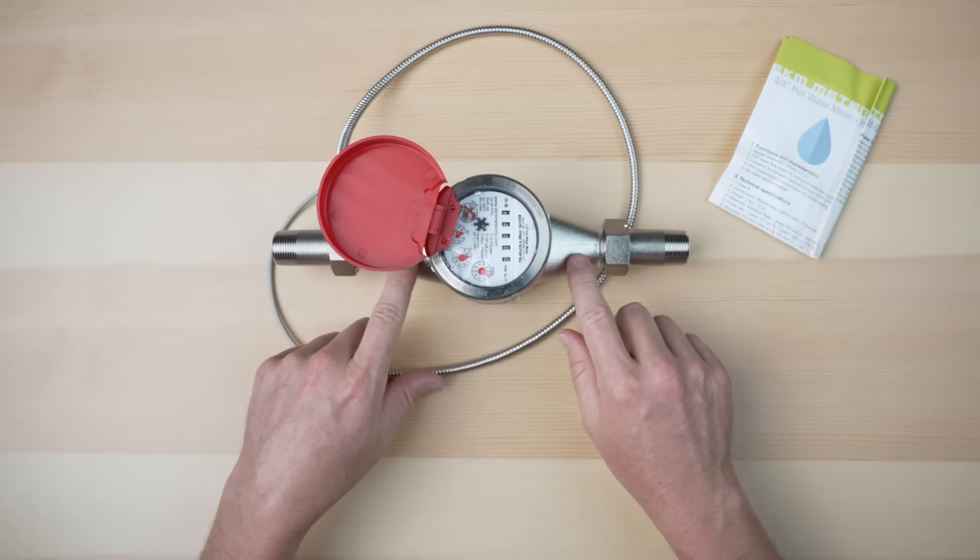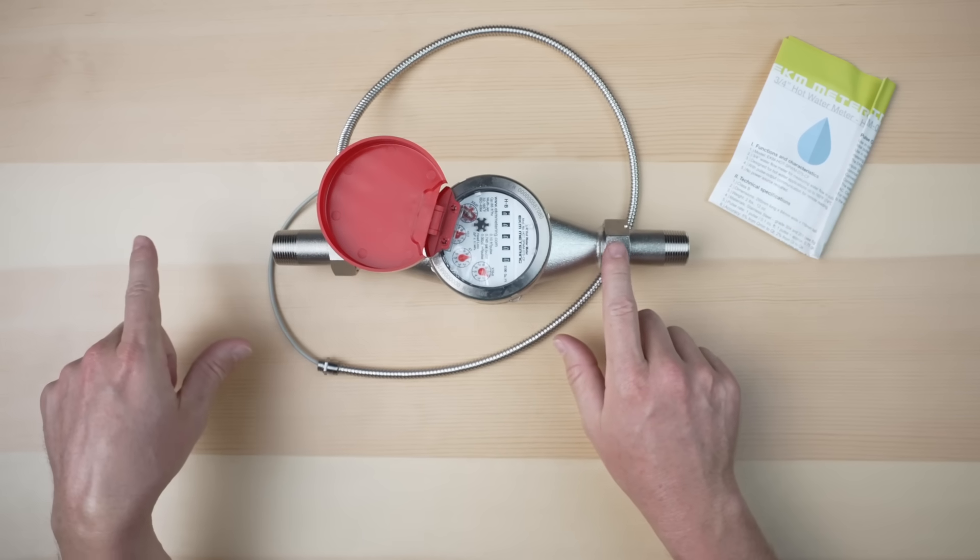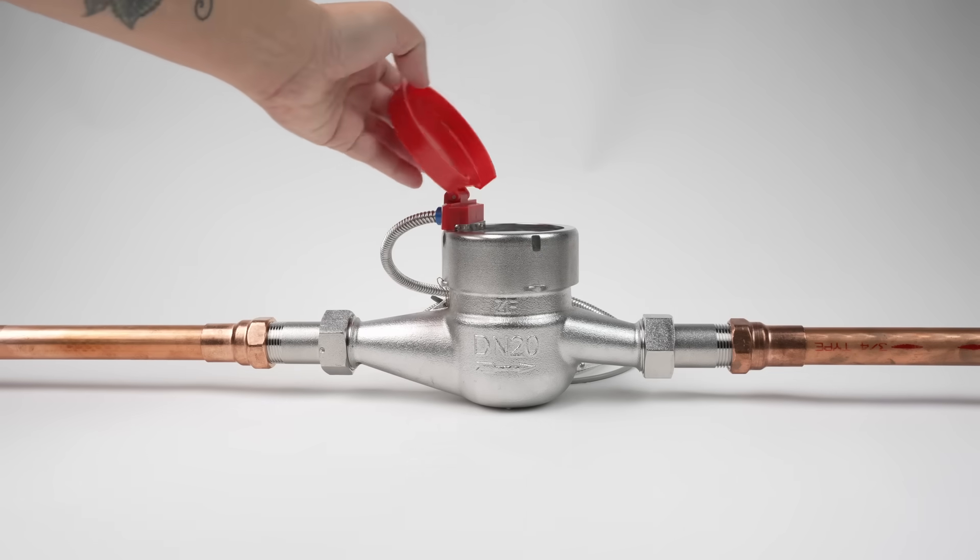For best accuracy, you want to install a straight piece of pipe before and after these two fittings. Before needs to be 10 times the diameter of the pipe. After is five times the diameter of the pipe.